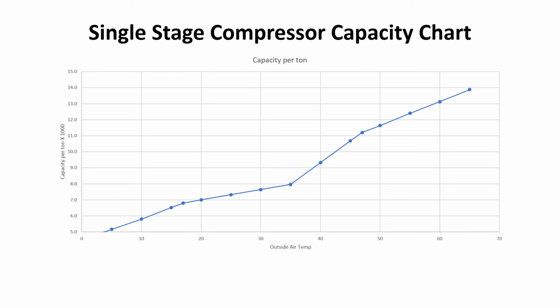So this is the capacity of a single stage system, if you will. Down here on the bottom axis, we have the outdoor temperature ranging from 0 all the way up to 70. The capacity over here is the capacity per ton. So basically what we can see, sure enough, at 65 degrees, wow, we're above our full rated capacity. That's good news. By the time we get down to, say, 47 degrees, we're right at about 12,000 BTUs per rated ton, exactly where we'd be.